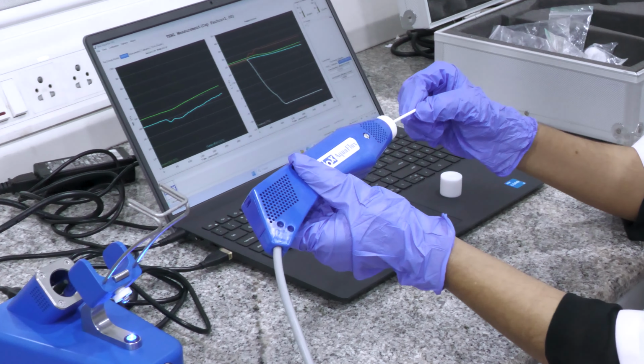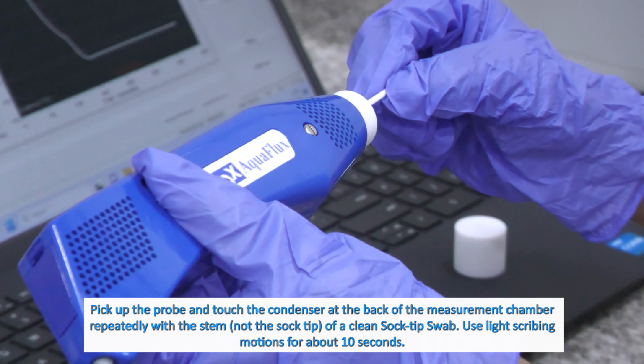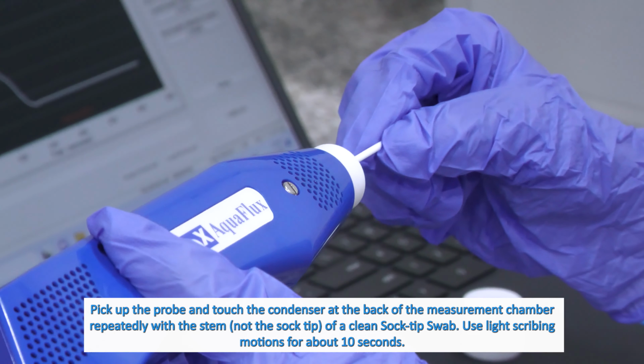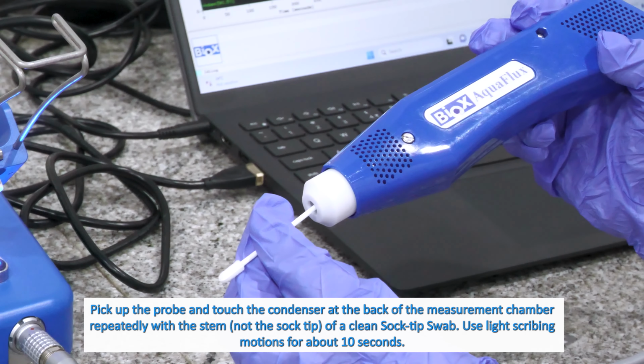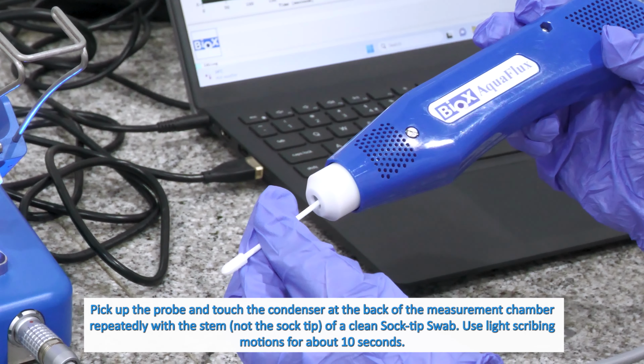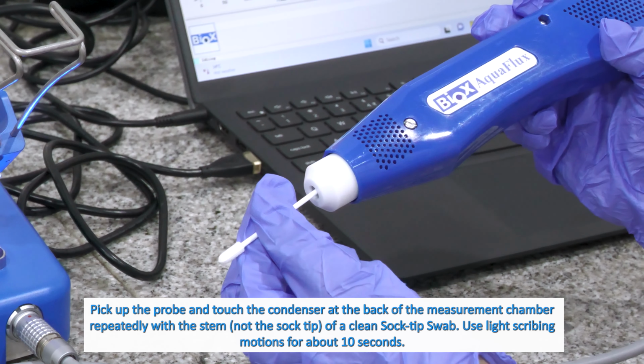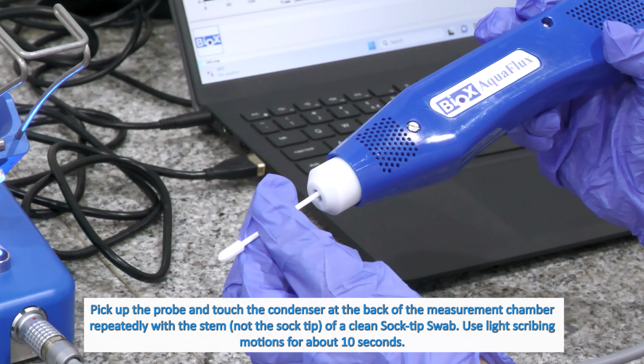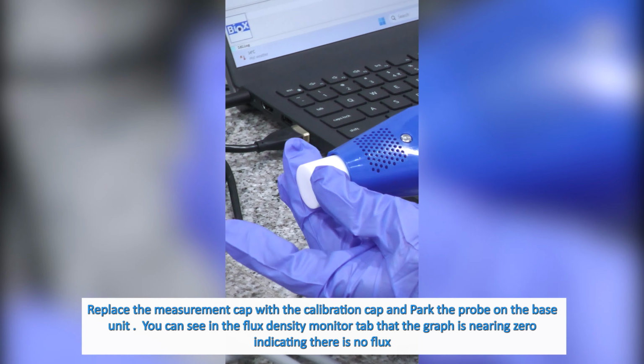Pick up the probe and touch the condenser at the back of the measurement chamber repeatedly with the stem, not the sock tip, of a clean sock-tip swab. Use light scribing motions for about 10 seconds. Replace the measurement cap with the calibration cap and park the probe on the base unit.